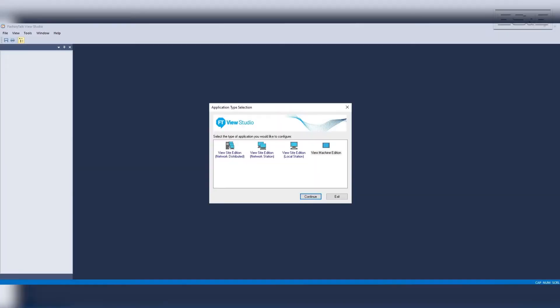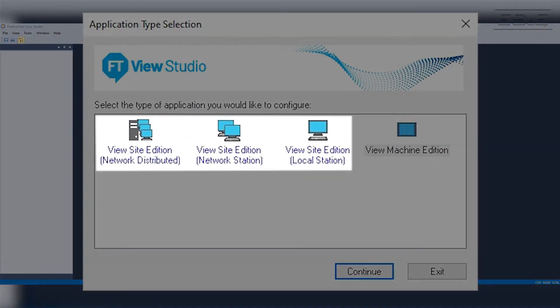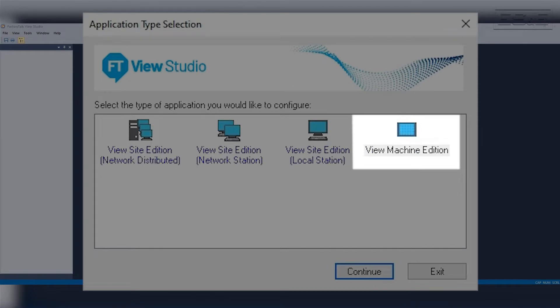There are two potential methods to create a new application. The first method is to open FT View Studio, then select Machine Edition and then select the hardware. The second method is to open Studio 5000, select FT View, and then select the hardware. If you have FT View Studio Enterprise, it will show both Site Edition and Machine Edition. If you have FT View Studio for Machine Edition only, it will open directly to ME without needing to select it.